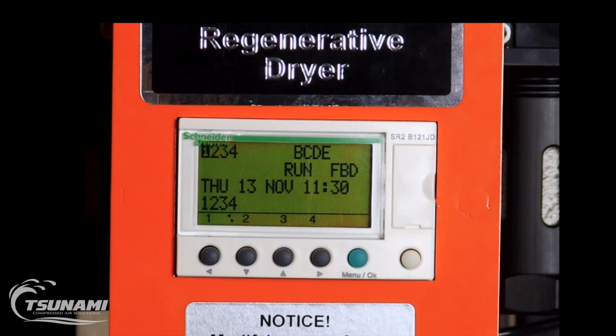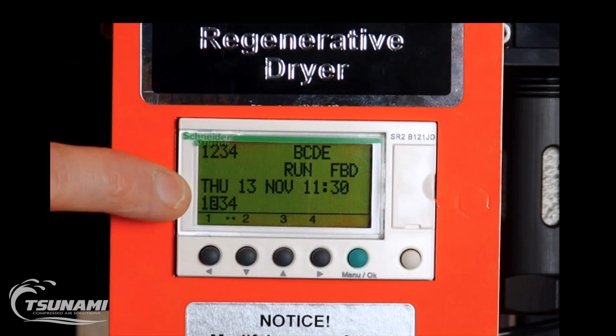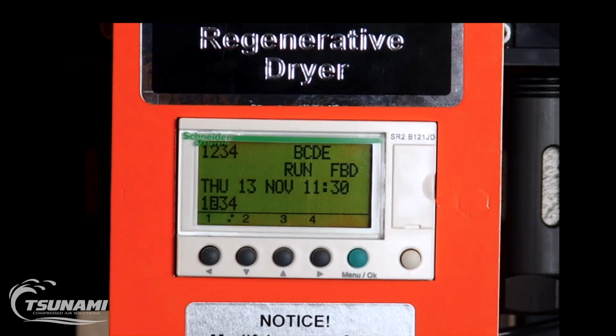That could be 1 minute, it could be 2, it could be 5. Let's just say after a period of time, the compressor then has a demand to generate air, and it turns on, which then opens the dry contact in its control. It then pulls the signal away, and notice that the PLC is now putting the dryer into a run mode in order to dry air that is going downstream for its application.